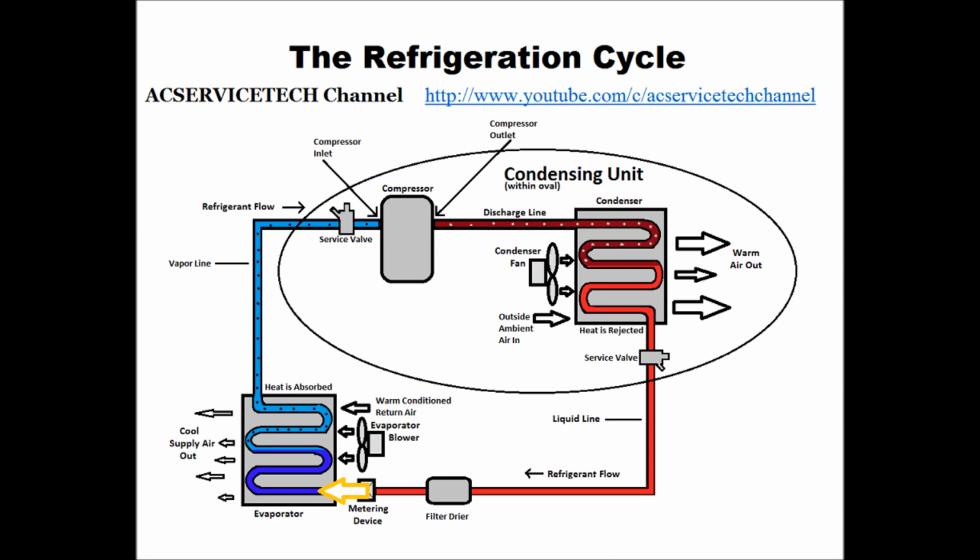A very easy way of remembering what superheat is: it's the temperature increase in vapor form in the evaporator coil. You can simplify it down to that, because there's only one spot where there's vapor in the evaporator coil, and it's after the saturated state. You'd take your temp reading and pressure reading right after it gets out of the evaporator coil, but we usually don't have ports there, so we take our reading as a total superheat out at the compressor. But basically, superheat is the temperature increase in vapor form in the evaporator coil.